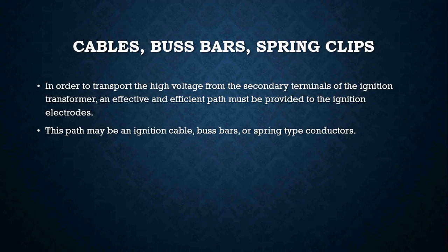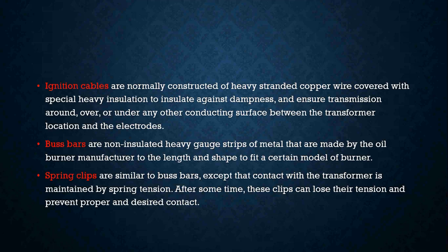So in order to transport the high voltage from the secondary terminals of the ignition transformer or solid state igniter, an effective and efficient path must be provided to the ignition electrodes. Okay, and those paths can be a couple different things. They can be ignition cables, they can be bus bars, or they can be the spring type conductors. Now these are the things that you're going to see on the bottom of the ignition transformer or solid state igniter. Now your ignition cables are normally constructed of heavy stranded copper wire covered with heavy insulation to insulate against dampness and ensure transmission around, over, or under any other conducting surfaces between the transformer location and the electrodes.